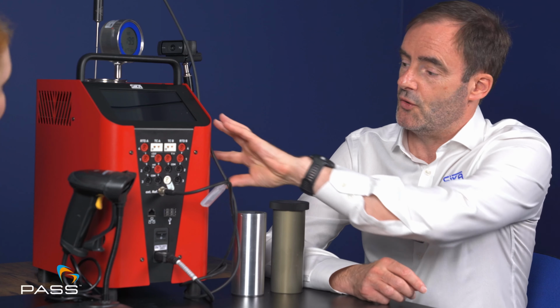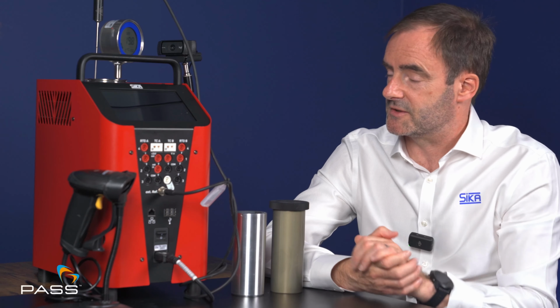Yes, certainly. So this one shows with the instrumentation that we offer. You can have it with or without this instrumentation on the front panel. But what this allows us is that we can then calibrate 2 devices under test, along with an external reference sensor, or use the internal reference sensor. And then from that, we can then calibrate those 2 units completely. And then at the end of that, give the end customer a PDF document that they could then download via the USB ports at the front.